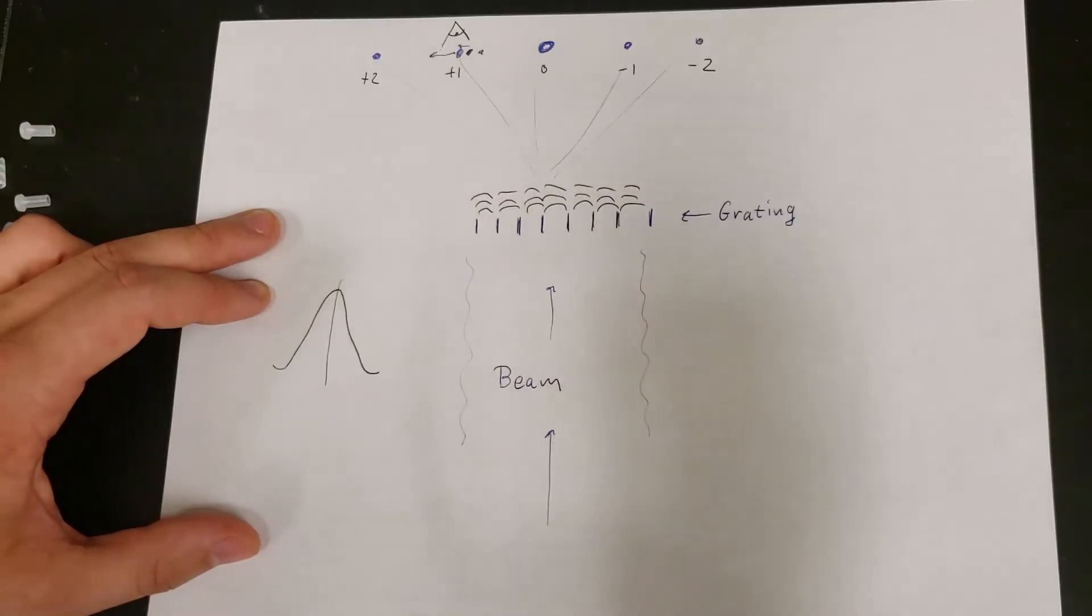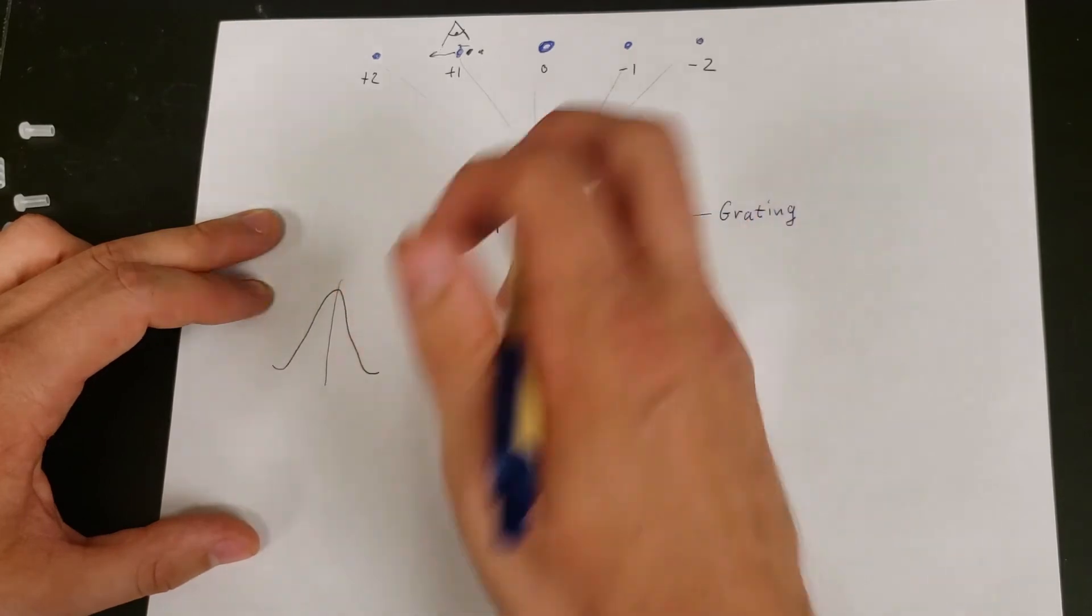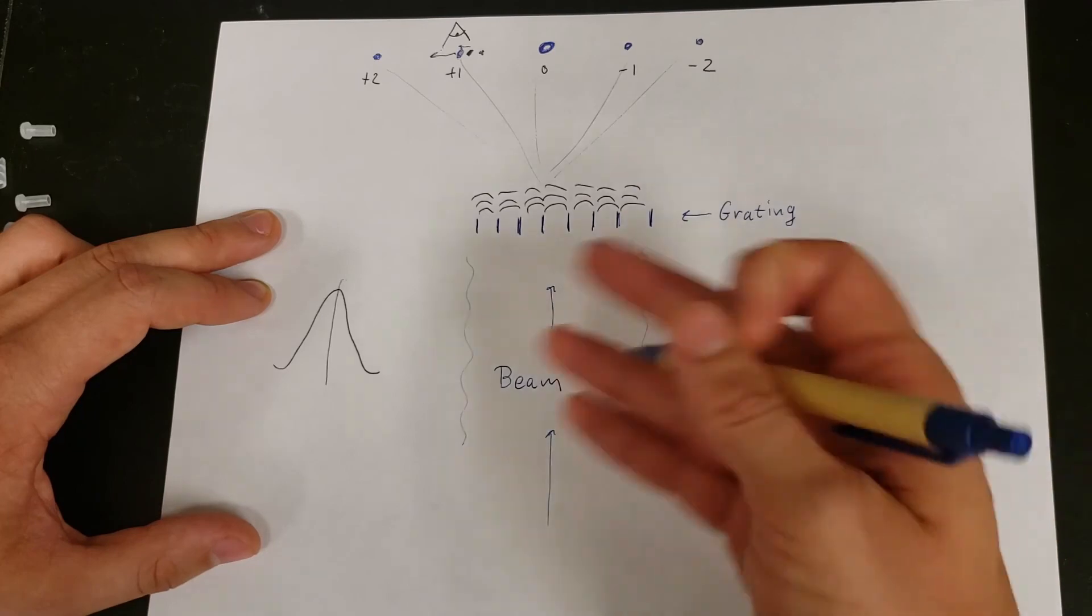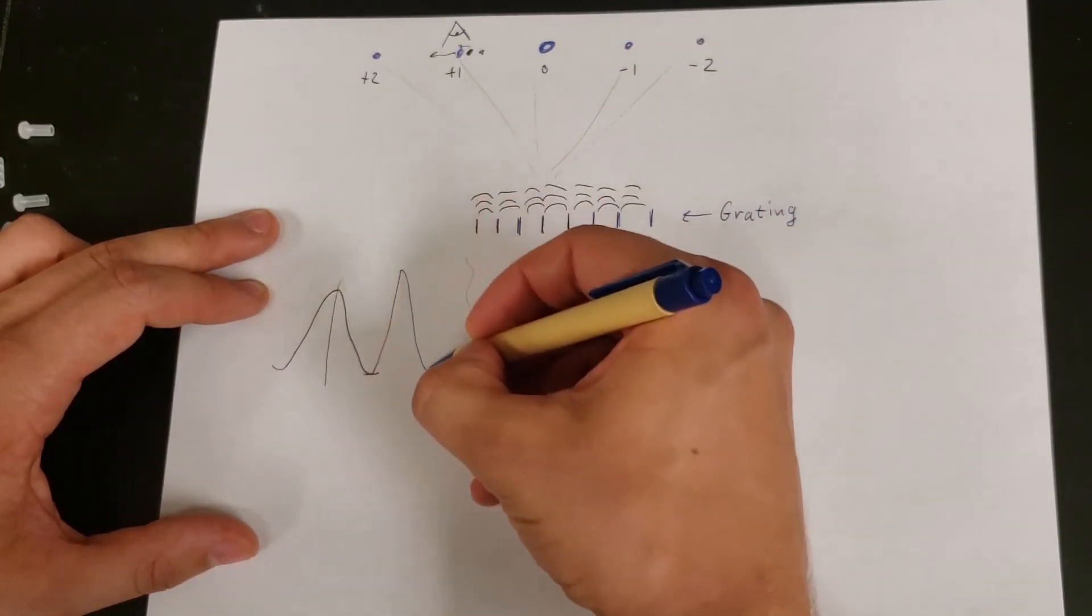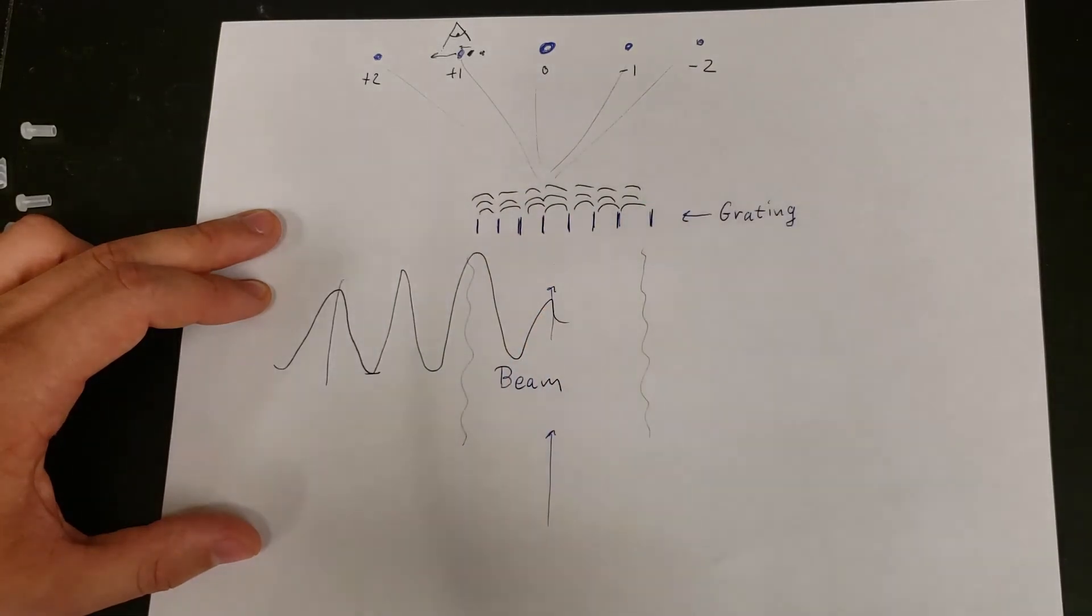You can simply repeat that for all the different settings of the grating here. And of course, the manufacturer's done a calibration knowing that with this particular orientation, then it's looking at this particular wavelength. And of course, I've explained this in sort of a step-by-step manner, but in reality it happens just continuously like this and it just records the power that it observes. So that's essentially how the OSA ends up creating this spectrum of the light that's coming in.